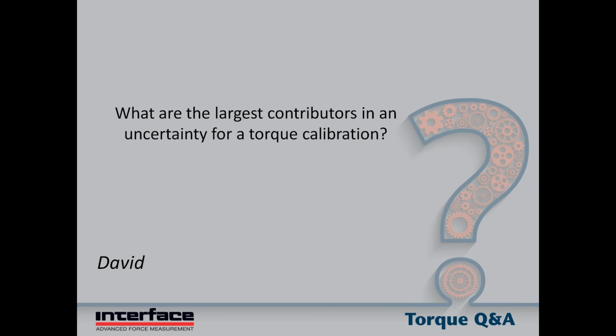Another thing: if you're using moment arms, again, you can have a calculation of the applied torque, but if that arm is bolted directly to the sensor, there's also a lot of overhung moment applied to the sensor. And so that can adversely affect the output of the sensor. You think you're applying torsion, but you're really applying an increasing torsion along with an increasing bending. And so in the application, if the customer or the user doesn't have any bending, then you've really calibrated it in a condition under which it's not going to be used.